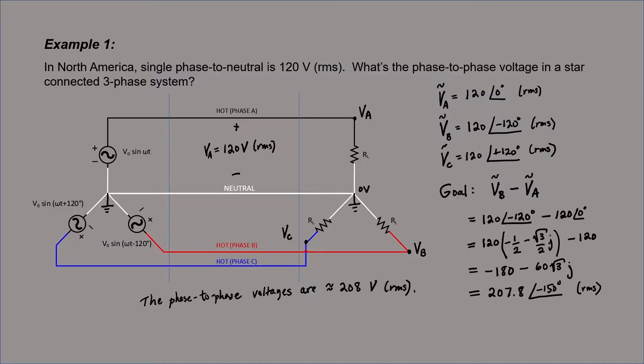From the phase information, we find that it's negative 150 degrees. What it means is that the voltage that I measure or the waveform is going to be out of phase with either phase A or phase B. Normally, though, a voltmeter won't tell you the phase, it'll only tell you the RMS voltage. I'll get that same RMS voltage, 208 volts, regardless of which two phases I measure between.